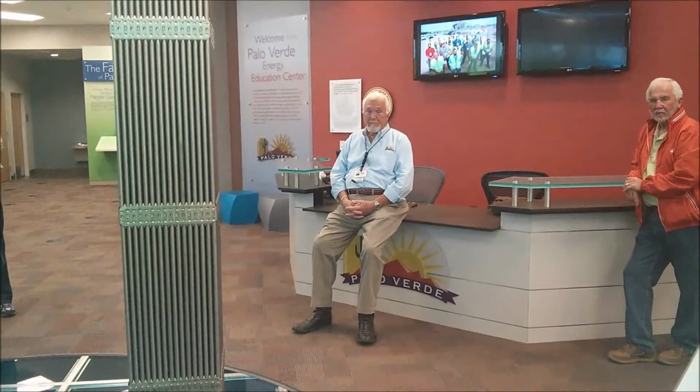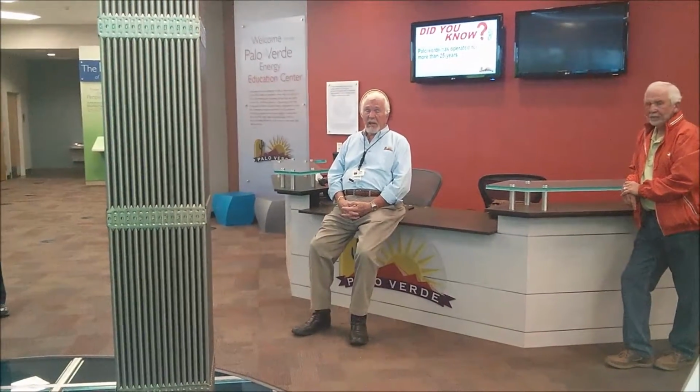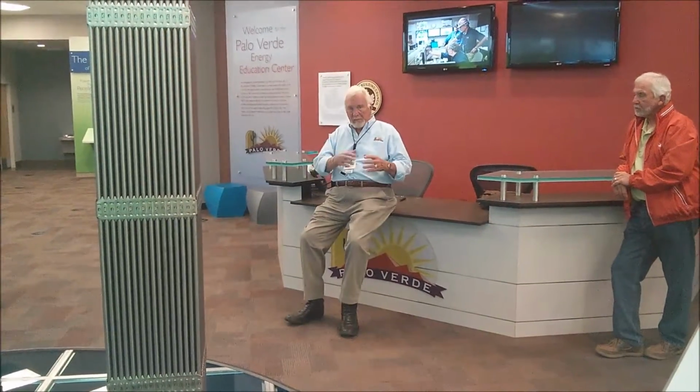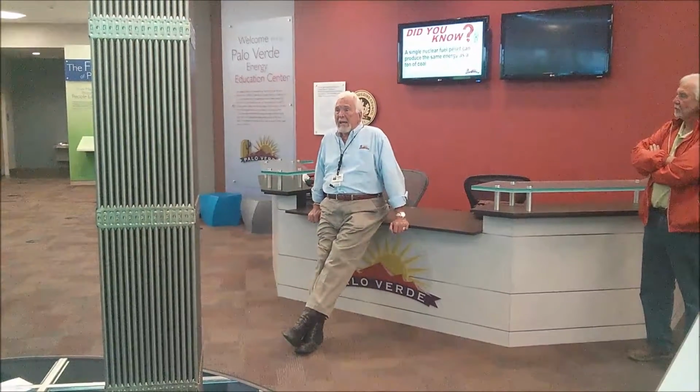So, what about why we can't have a Fukushima-style accident here? Well, number one, we're not very close to any tsunamis. Okay, so that's the main reason. We don't have our electrical system susceptible to a tidal wave, and that's what caused it at Fukushima. What electrical systems we do have are triple backed up. We've learned from Fukushima, and we had 2 backup levels. We've gone to 2 more, so we have a total of 4 backup levels.